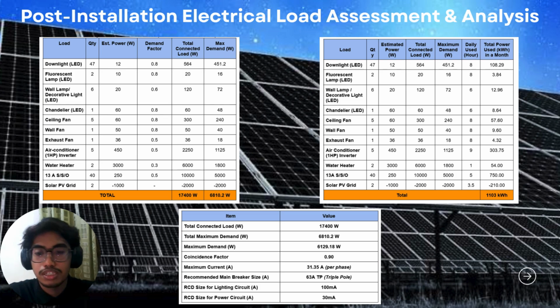As before, the maximum demand formula equals total maximum demand times the coincident factor. We get the maximum current, the size of MCB, the overcurrent and the size of RCD.